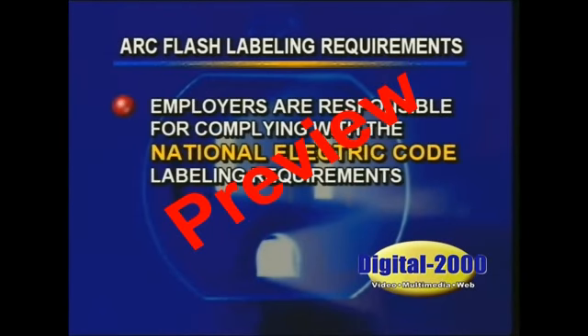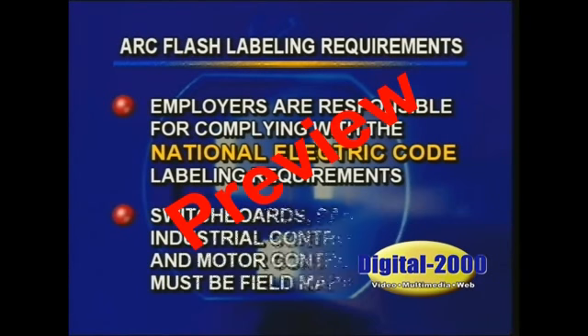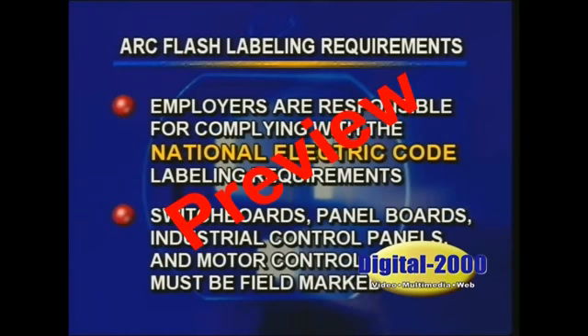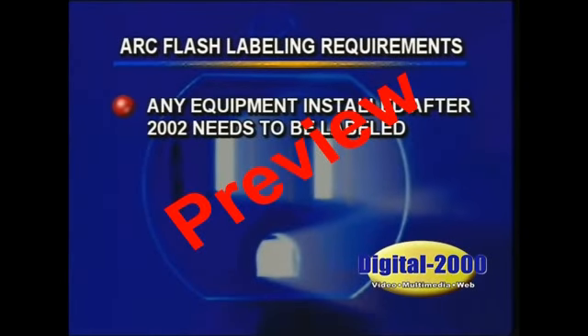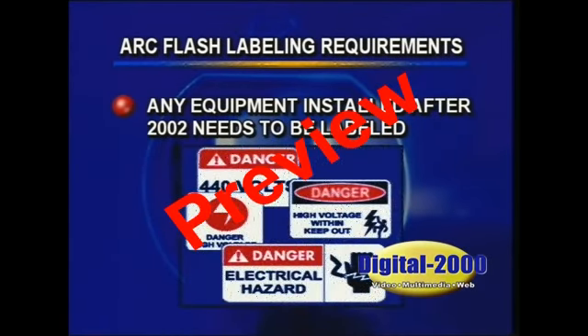Employers, not manufacturers or installers, are responsible for complying with the National Electric Code labeling requirements. Switchboards, panel boards, industrial control panels, and motor control centers must be field marked. Many companies are also marking conduits, disconnect switches, and any other equipment where the risk of arc flash exists. Any equipment installed after 2002 needs to be labeled. For equipment installed before 2002, labeling must be applied if any modifications or upgrades take place. Smart employers are taking the safe, efficient approach of labeling all their electrical equipment regardless of when it was installed.